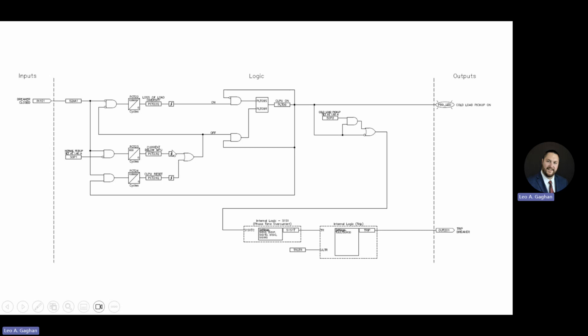Because this isn't being driven, we're going to have a 0, which comes up to this NOT gate as a 1. So if that's the case, if this breaker is open and this part of the logic isn't being driven for long enough, 108,000 cycles, however many minutes that is, maybe it's 15 minutes. If the breaker is open for 15 minutes, essentially, we are going to send a rising edge trigger, and as long as cold load pickup is off, it'll turn itself on. So cold load pickup is on, and we'll call it armed.